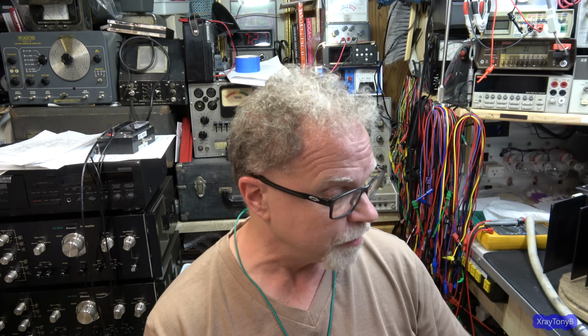So for those of you who may ask, what the heck's the point in having a 32 volt fuse when you could just stick a 250 volt one in there for everything, as long as the amp rating is the same? That's why. The 32 volt fuses have very high breaking current as opposed to the higher voltage ones. They have a different way that they will fail than the 250 volt ones. Now, why am I telling you all this? Well, it's because when I went to order these fuses, I noticed that there were the 32 volt and the 250 volt versions.